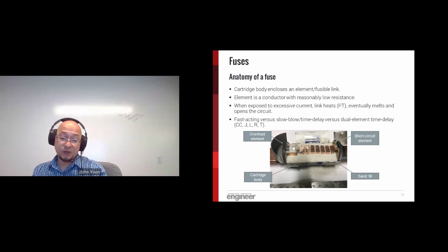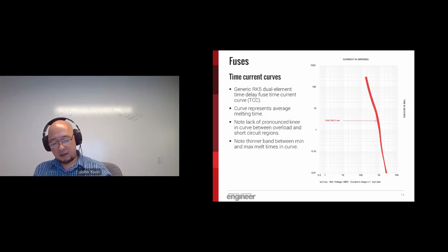To address this issue, the fuse industry came up with the concept of a dual element fuse. Now, that's exactly what it sounds like. You have two separate elements connected in series together, one optimized for the low magnitude overcurrent condition and the other for the high magnitude fault condition. The vast majority of fuses that you encounter in low voltage power distribution systems will be of this dual element type. So let's move on to how the element in the fuse reacts to various magnitudes of overcurrent.